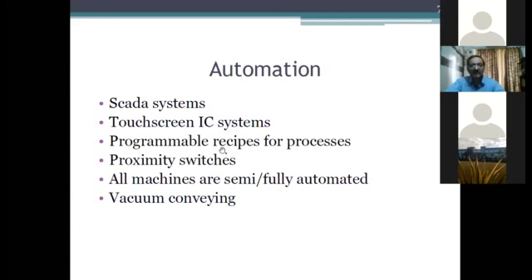Programmable recipes are there for the processes, where you can feed a recipe. Recipe means process parameters. If you are doing sterilization, you can feed the recipe that for 5 minutes this will happen. The rubber stoppers will be loaded into the machine.